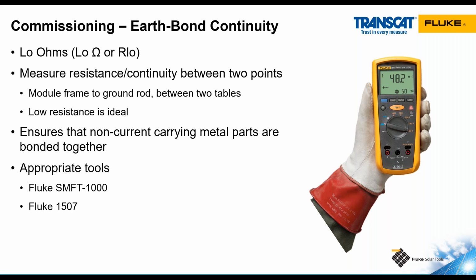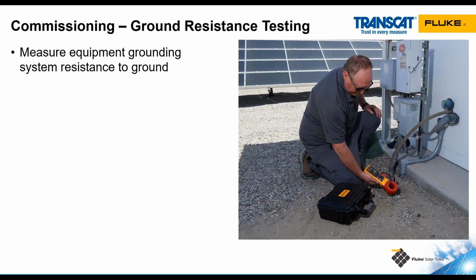There's a different IEC standard for this type of testing that requires a 200 milliamp test, which is a current level much greater than most multimeters are capable of doing. So we have the SMFT 1000 and the 1507 insulation resistance tester can both perform this type of a test at the 200 milliamp level. Important to make sure all those metal parts are bonded together.